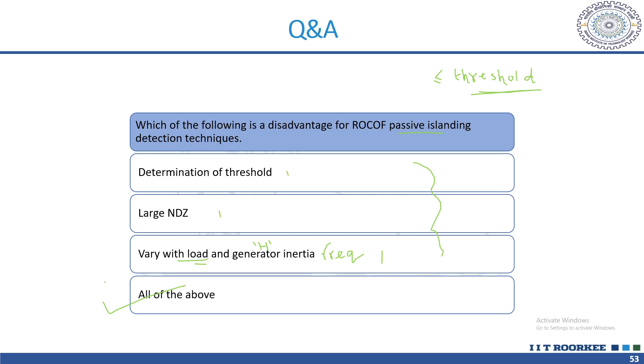Then all these techniques also have a large non-detection zone. And since it is with respect to frequency, frequency will also change when there is a load change or when the inertia of the generator changes. So basically the answer is all of the above. So all these are disadvantages for ROCOF as an islanding detection technique. Then a positive superimposed negative impedance implies what?